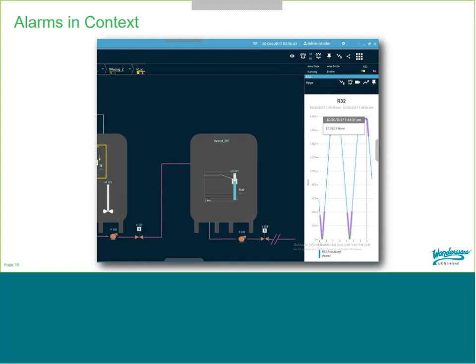You can see how long it was in an alarm state, what the reason was, and who acknowledged it. It's a very neat thing that we've not really had before from a historian trending perspective. You can now very quickly see where your alarms lie over your process data, with zero engineering in this case.